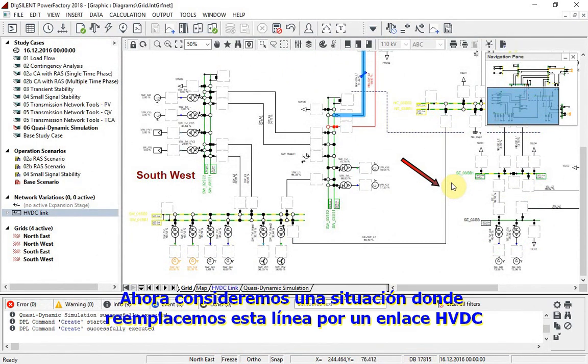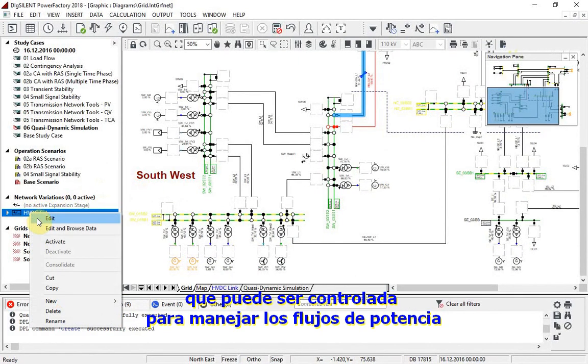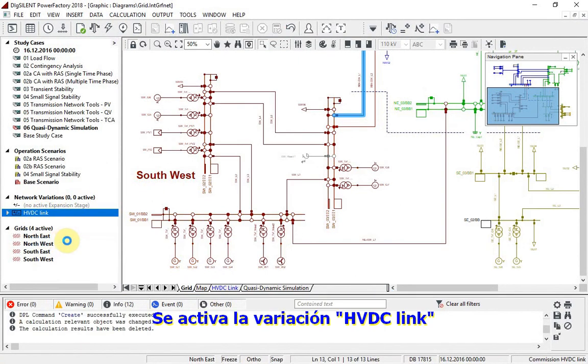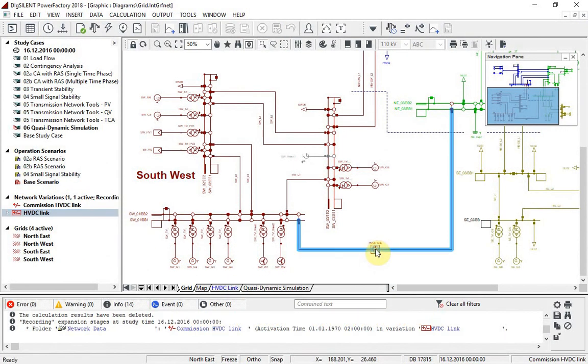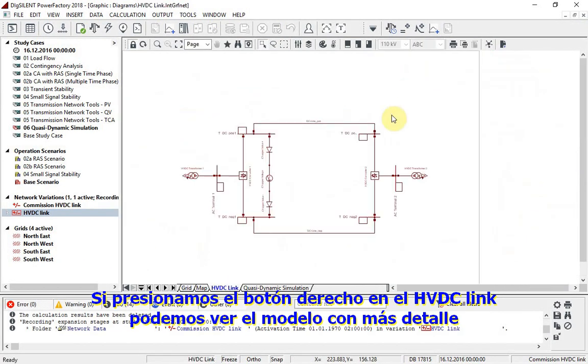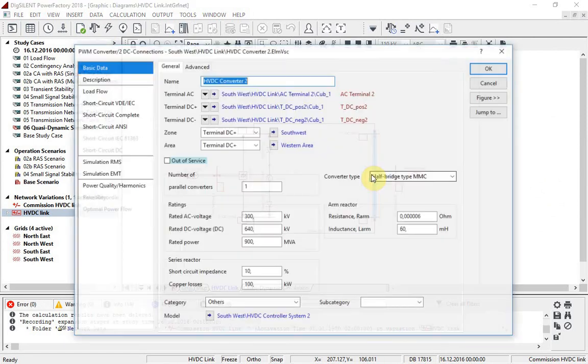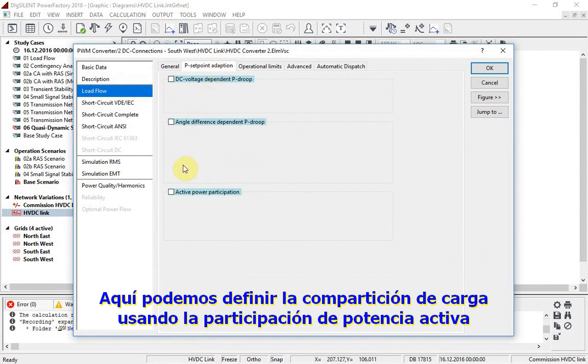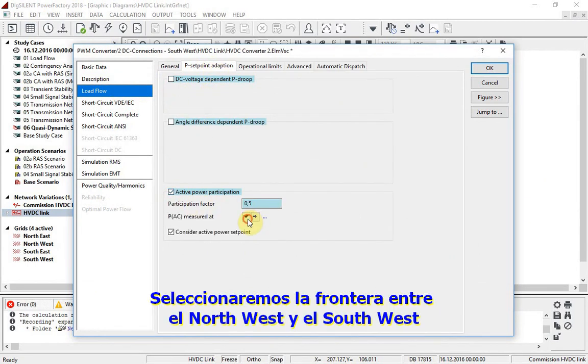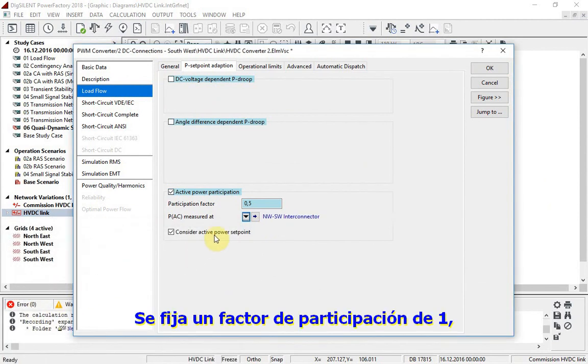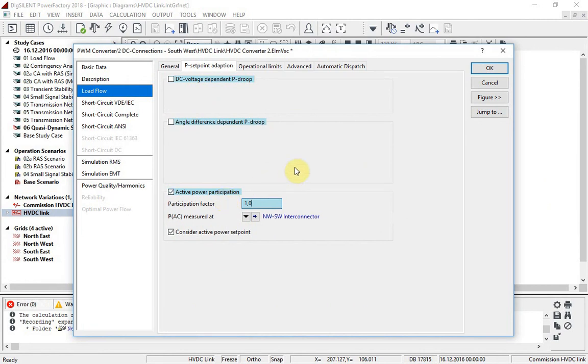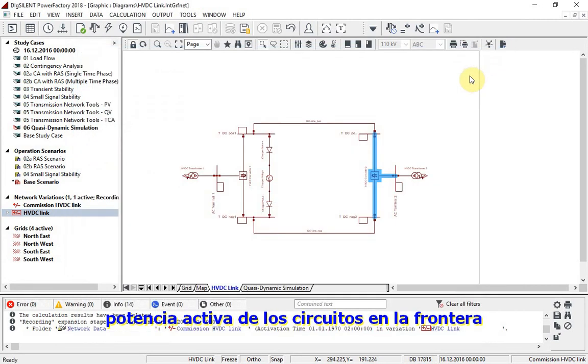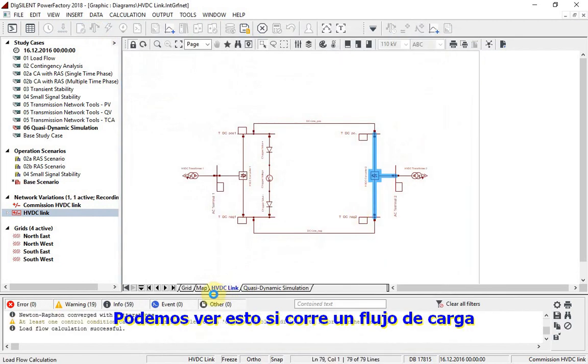We will now consider a situation where this line has been replaced by an HVDC link which can then be controlled to manage the power flows. The HVDC link variation is activated. If we right-click on the HVDC link, we can look at the model in some detail. Here is where we can define the load sharing, using active power participation. We will select the boundary between the north-west and south-west. A participation factor of 1 is set, which means that the HVDC link will carry the same active power as the circuits across this boundary.